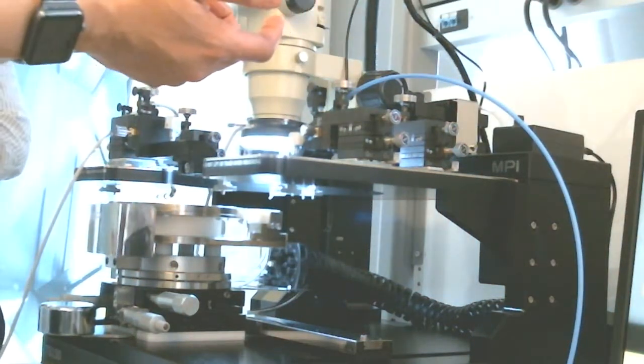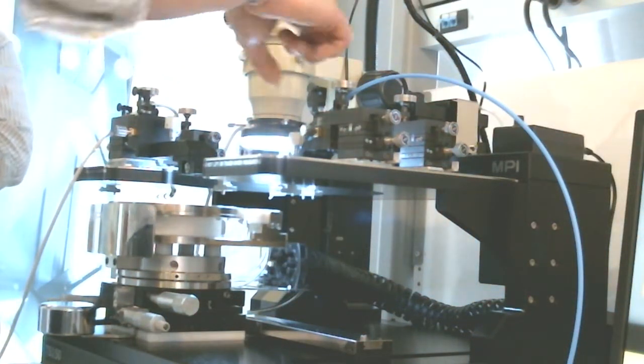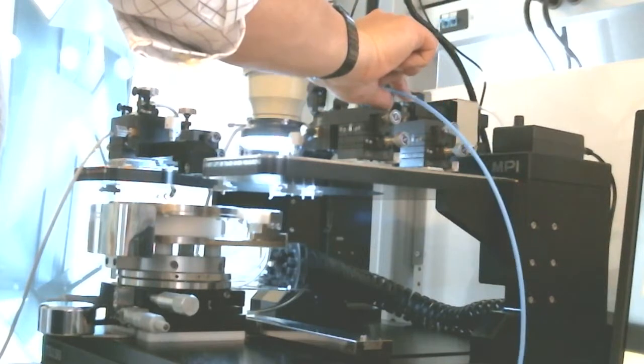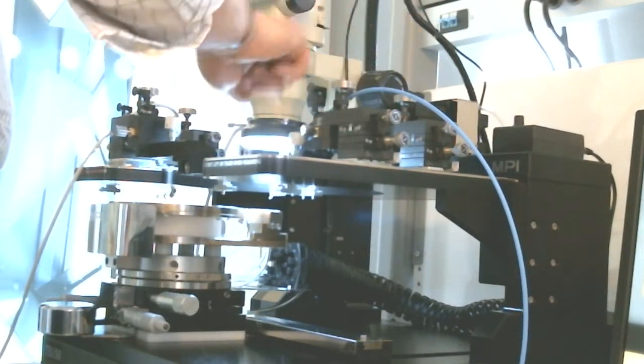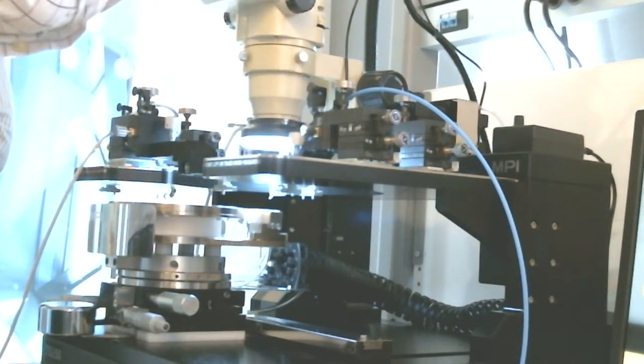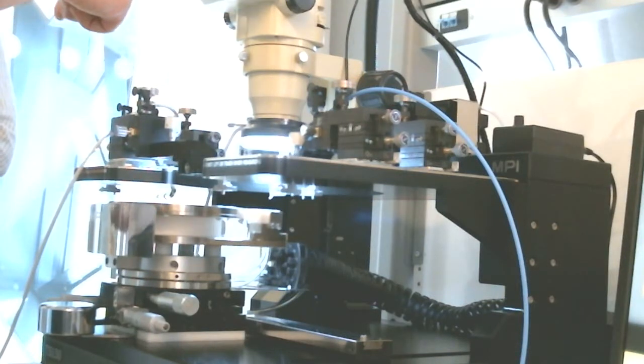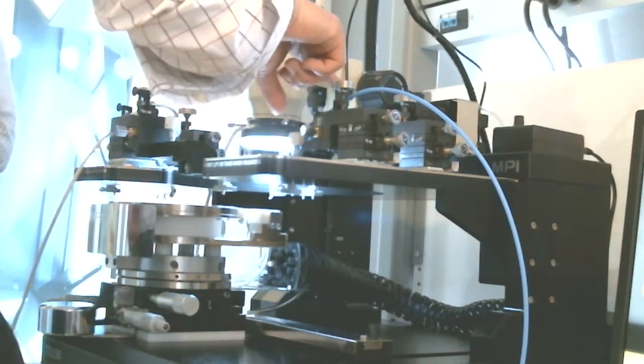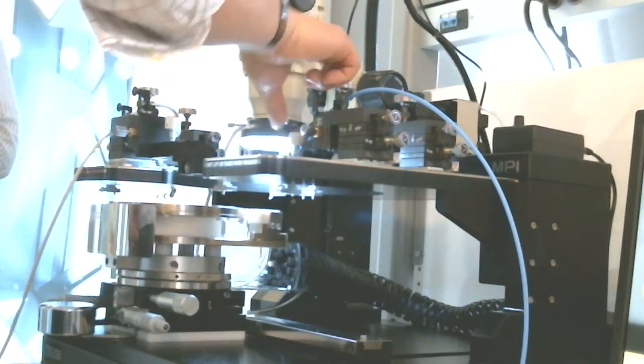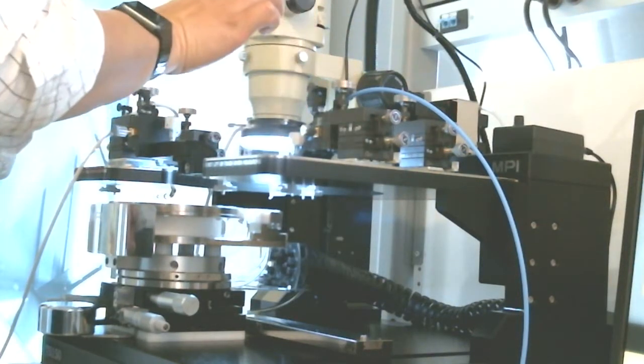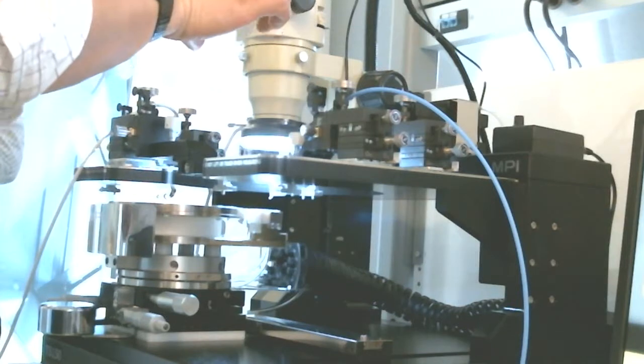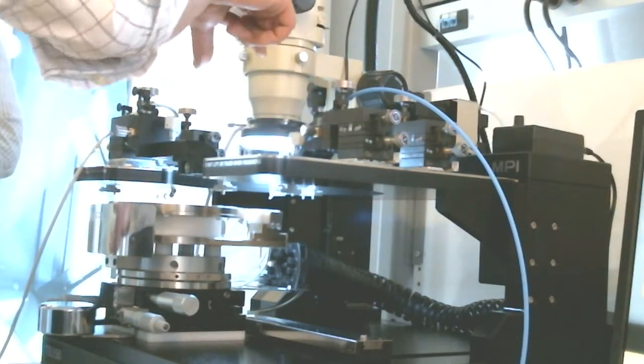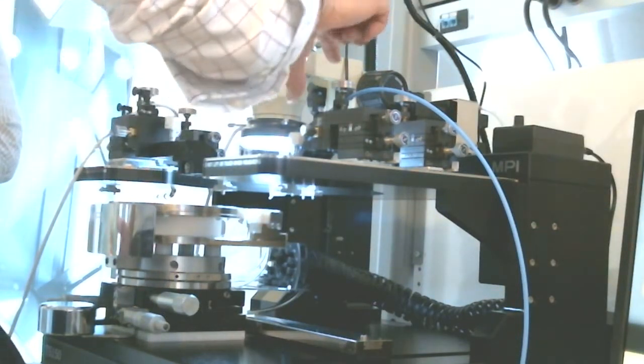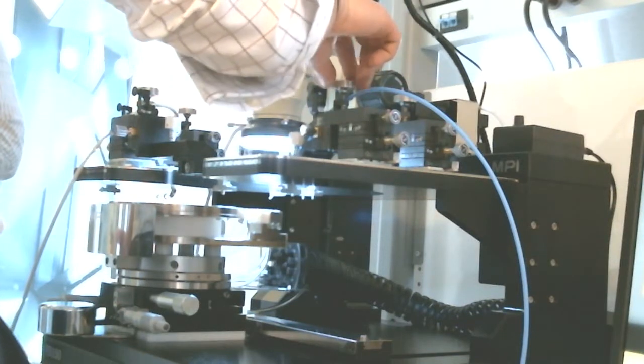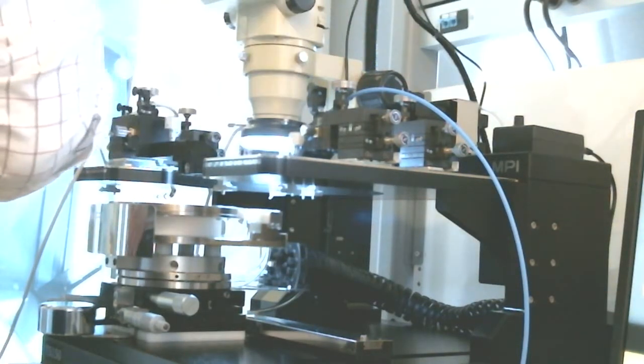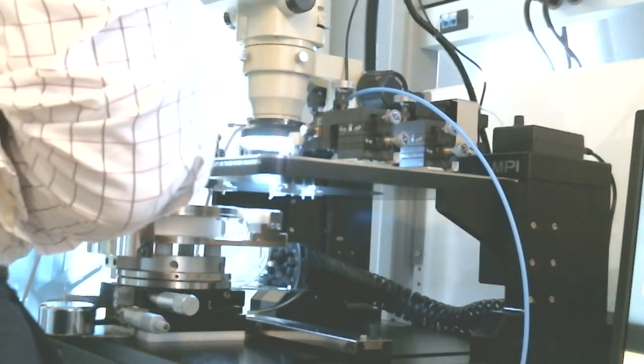But honestly, the best solution would probably be attachment here and another one here. Because if you put it here, the fact that this moves and this doesn't move means the cable will actually move more. We put it here so that the whole thing moves together, because when you're making really high frequency measurements, this moving actually could change the measurement. That's why we attach it to the part that actually moves up. And especially for RF, right? Yeah, RF and millimeter wave work.